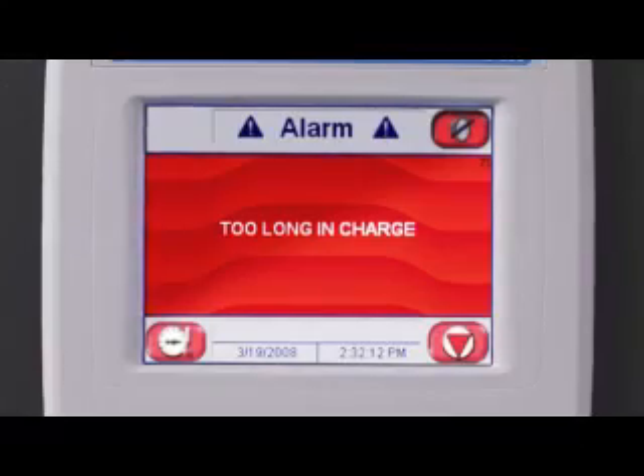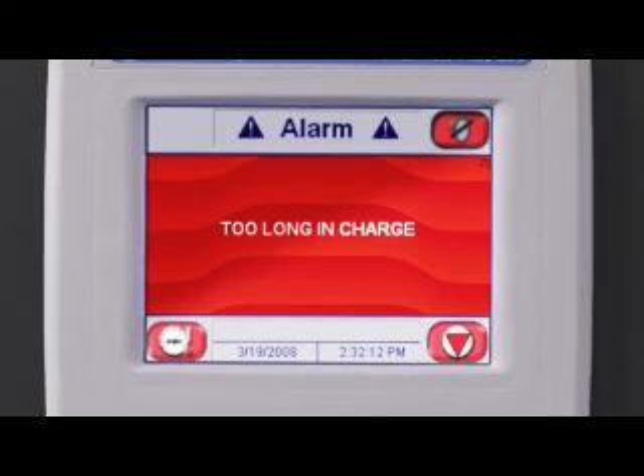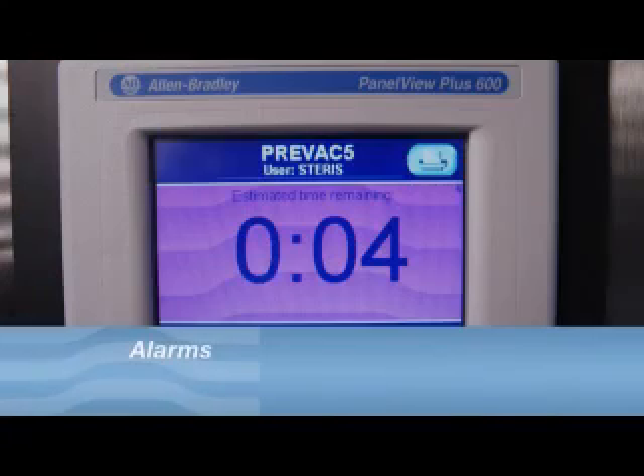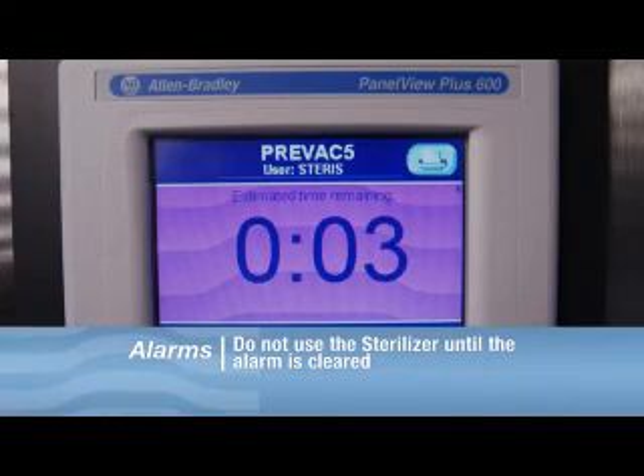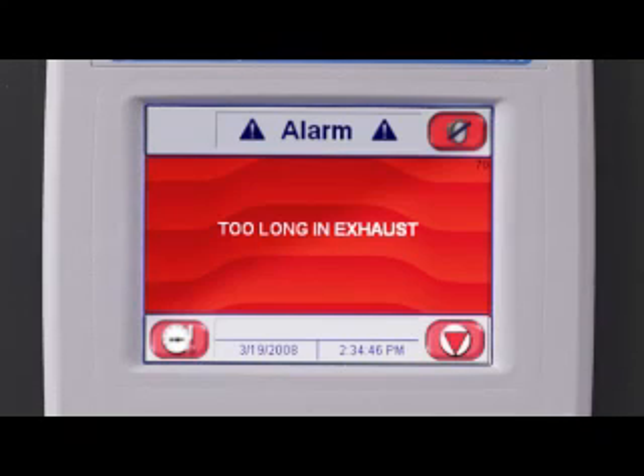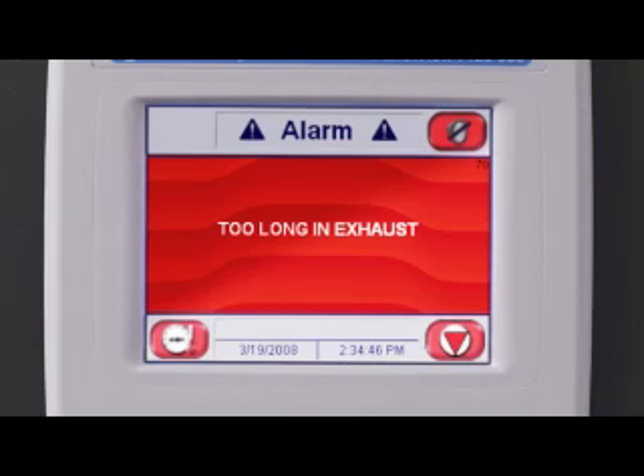When the sterilizer experiences an abnormal condition, an alarm display will appear along with an audible tone. The display indicates the problems as determined by control sensors. The alarm can be silenced, and depending on the nature of the alarm, the sterilizer will either abort the cycle or resume the cycle. Some alarms, such as those that indicate a phase is taking longer than expected, are just to alert the user. As soon as the temperature and pressure settings have been reached, the cycle will resume.